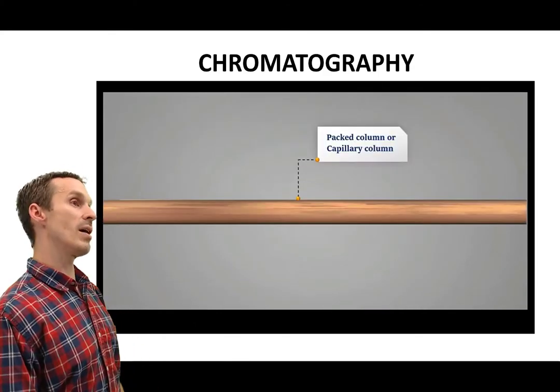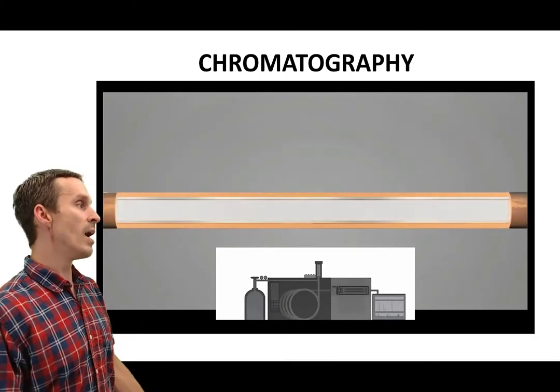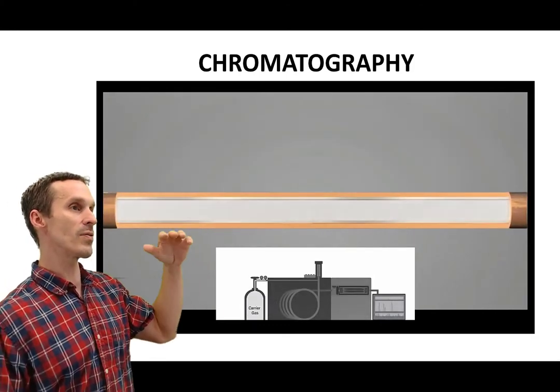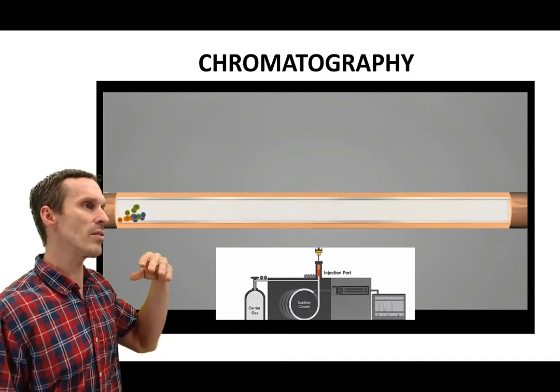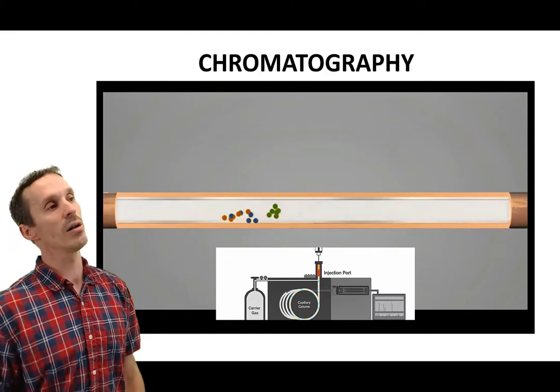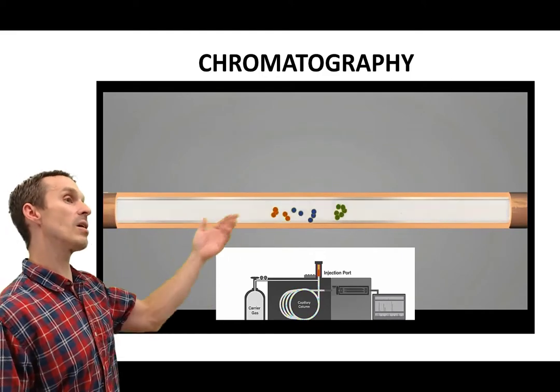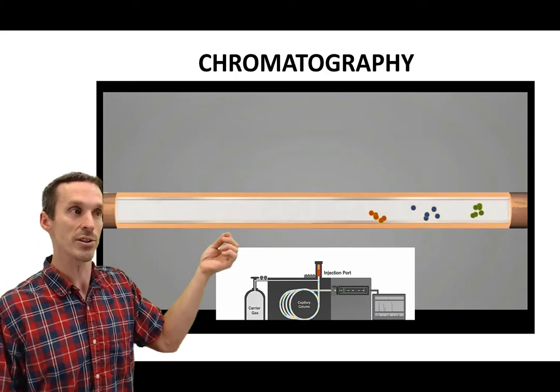Now the sample is going to travel down this really long column. The column might be like a hundred meters long, and the inside of it has a coating that allows for different retention. Some analytes stick to that surface and others not so much. As the analytes are blown through that column, you notice that some of them have a head start, some of them are gaining on the others. They sort of cluster up like that and you end up with a separation.